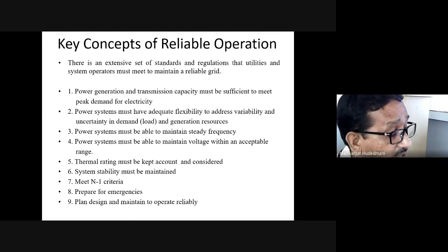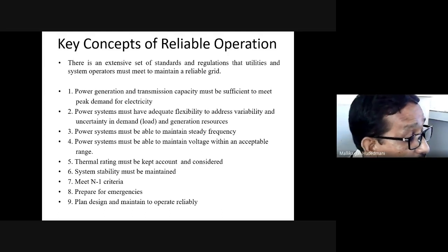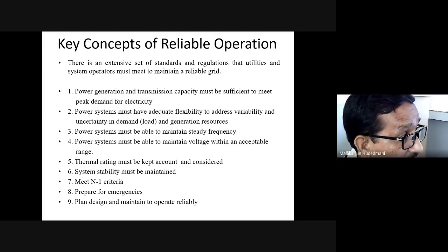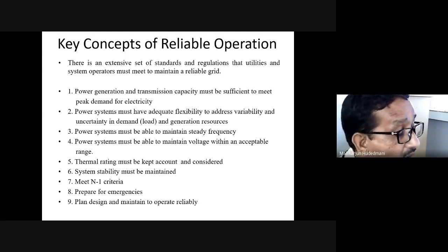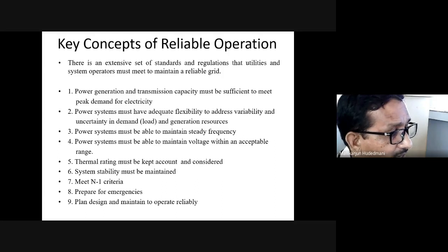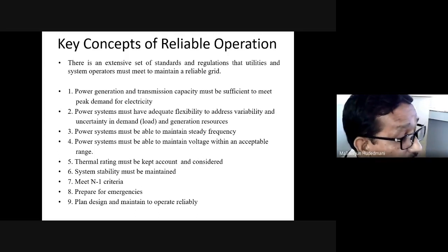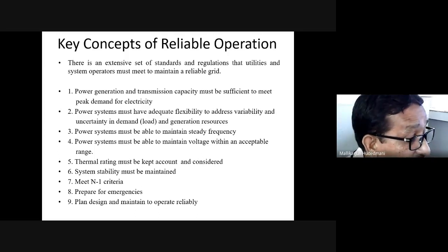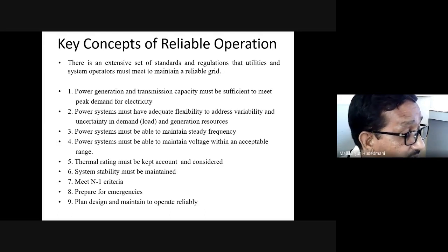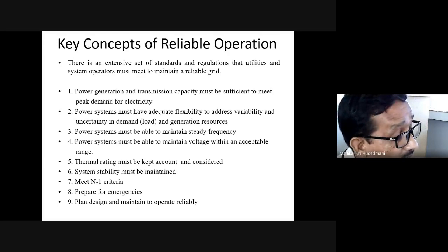Let us make it a reserve. That reserve is readily available, by quantity in megawatts. If a certain generator suddenly collapses, it must be able to meet that. Or if a certain generator suddenly reduces its capacity to half or a certain value in megawatts, this spinning reserve value, designed or kept spare by the operational aspect, is able to cope up with that loss immediately. In that way, an N-1 criterion with respect to generator, transmission line, and other components, I can define and keep my system ready to cope up during such a situation.